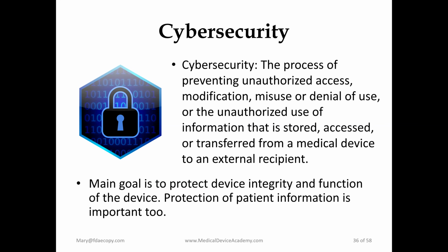And obviously, if somebody is able to modify the software in a malicious way or access information that they're not supposed to use, it's the responsibility of the manufacturer to try to identify those threats and to mitigate to the extent possible the risk of that happening. So that's what the FDA expects to see.